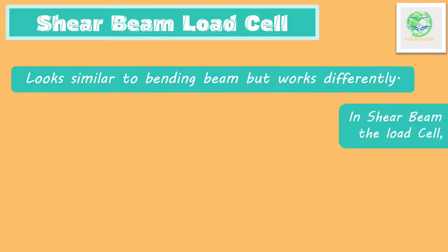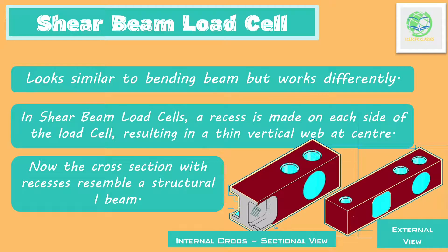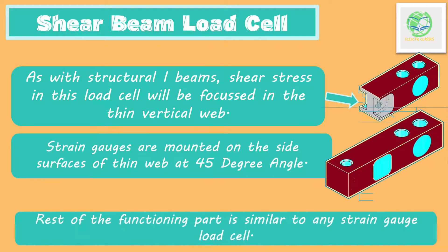Shear beam load cells look similar to bending beam load cells but are very different in working. In a shear beam load cell, a recess is made on each side of the load cell as shown in the diagram, resulting in a thin vertical web in the center. With this recess in place, the cross-sectional appearance becomes similar to a structural I-beam. As with a structural I-beam, the shear strain is focused in the thin vertical web. Strain gauges are then mounted on the thin web side surfaces at a 45-degree angle to detect strain. The rest of the functioning is similar to any strain gauge load cell.